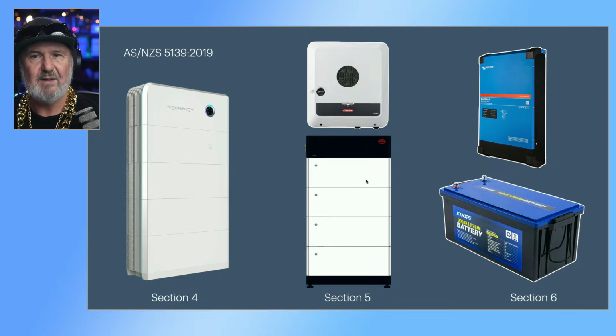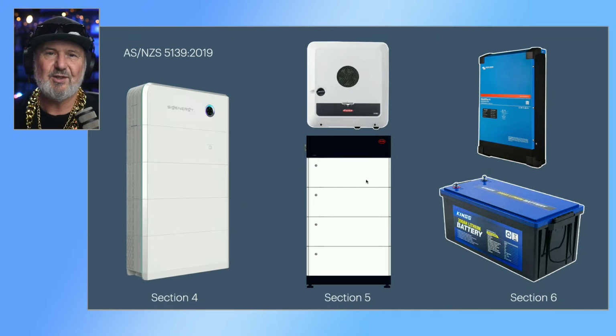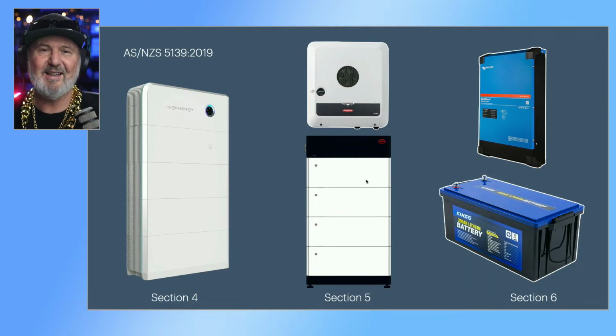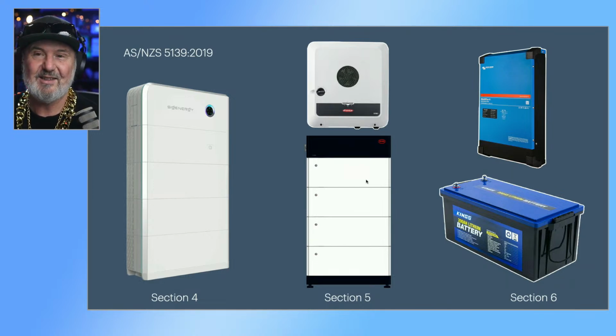But both Sections 4 and 5 are put into a category where we're fairly confident in the product's reliability, or I should say safety. But Section 6, now I'm not casting nasturtiums, as Kath and Kim would say, for those who don't know Australian comedy history, who don't cast assertions, sorry. I'm not saying that Victron is a bad product or that the King battery is a bad product, but it's got nothing to do with the PCE. Section 6 is only about the battery. And in this case, this battery, even though it's a lithium-ion battery, isn't listed as a pre-assembled battery system compliant with the best practice guide.